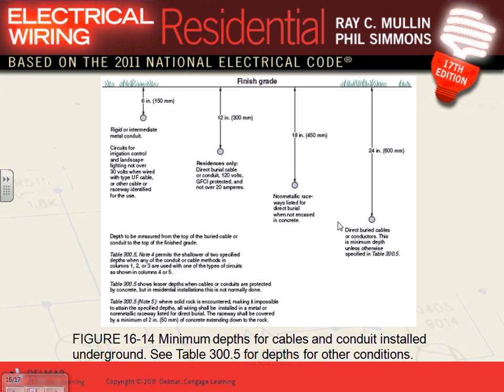If you do that, look at the limitation. 120 volt, 20 amp GFCI protected circuit, you can bury them up to a foot. Where would you put the GFCI? Right at the head, a GFCI circuit breaker, not a receptacle this time, to protect the whole cable. They allow you, residential only, to go 12 inches, so people are lazy, they don't want to dig too deep. 99% of the time, Nick, my friend, you're going to be either here or here.